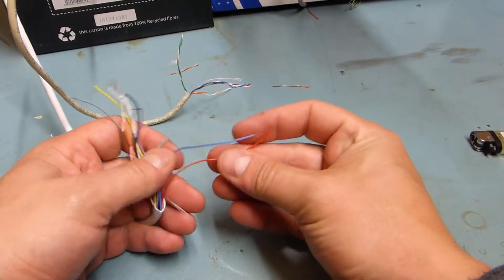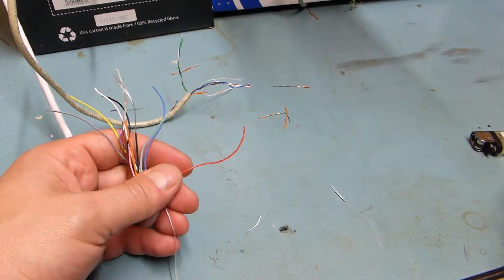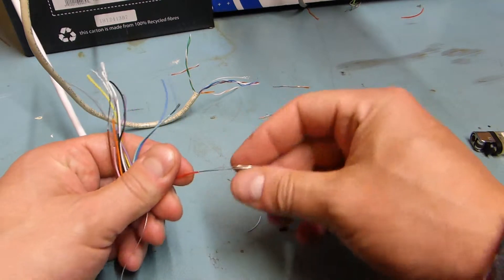Copper-coated aluminum is quite widespread. So this is a 12-core alarm cable. You can sort of tell that it's not right when you try to twist it. It won't twist properly.